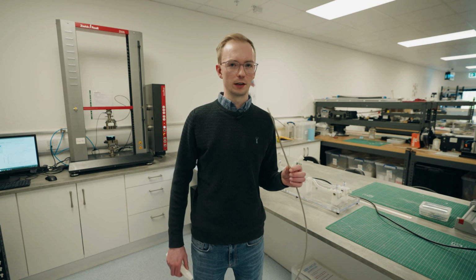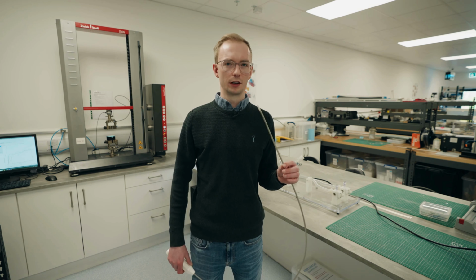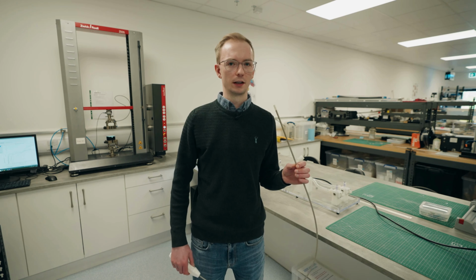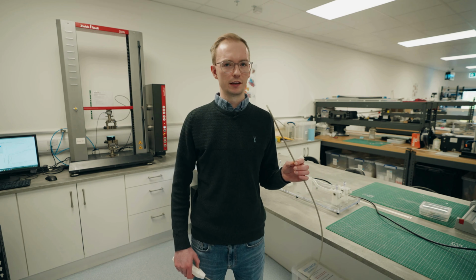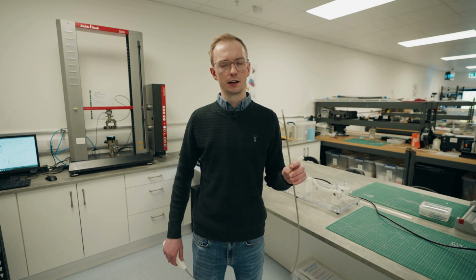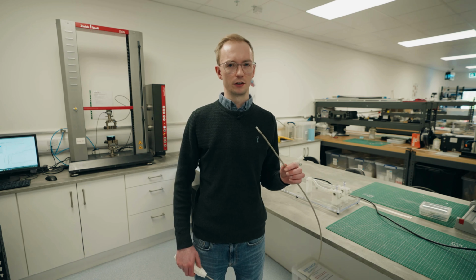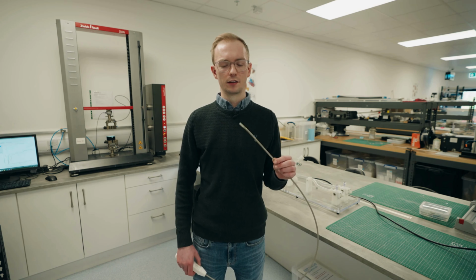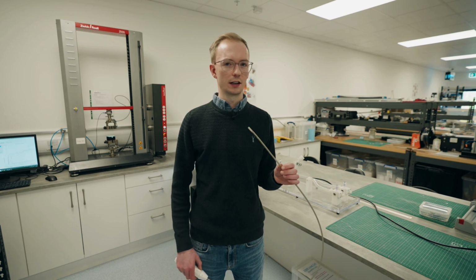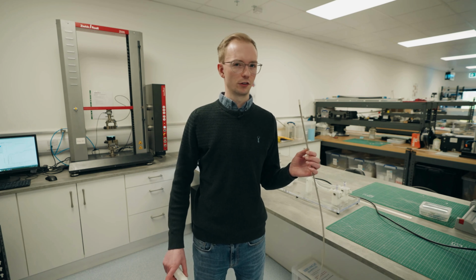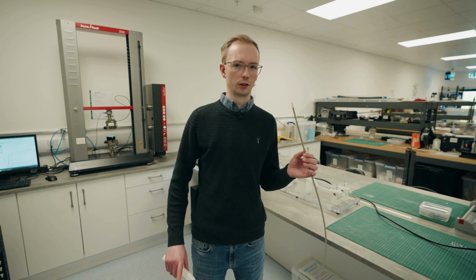So we have laser welding capabilities in-house, and we can actually do braid terminations with the laser welding. So it removes the need for PET or adhesives in our distal end, and it also gives us good strength by bonding the braid to the pull ring. In this example, it's a single direction, single plane catheter, but we can work it in two directions in one plane, or we can add a second plane and go in four directions.